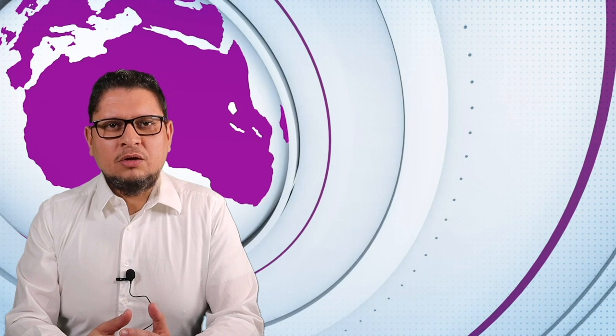So if you are a class 1 medical device manufacturer, don't just issue a declaration of conformity saying that you comply with the EU MDR. Have the right documentation to show that, because you may be visited by an authority.